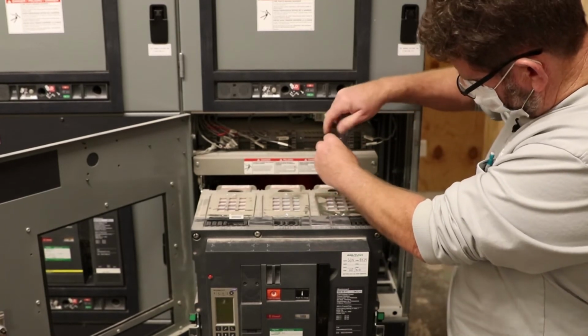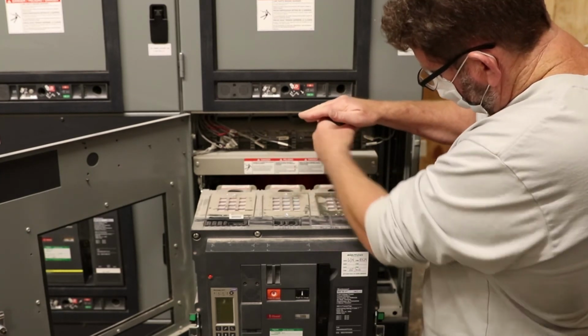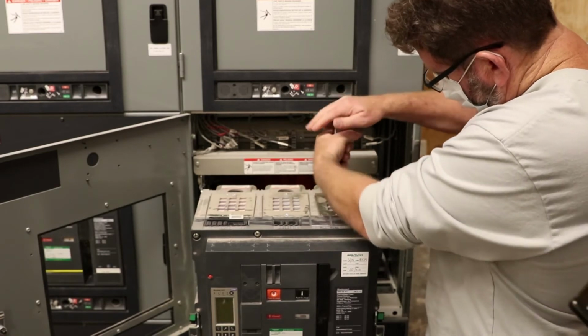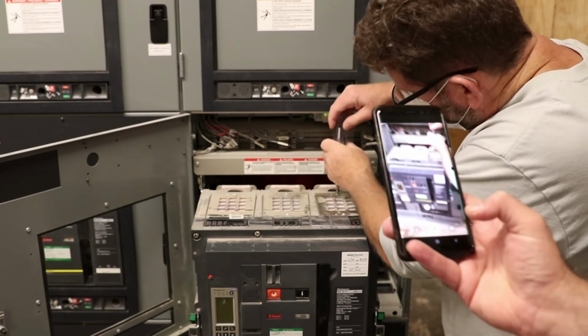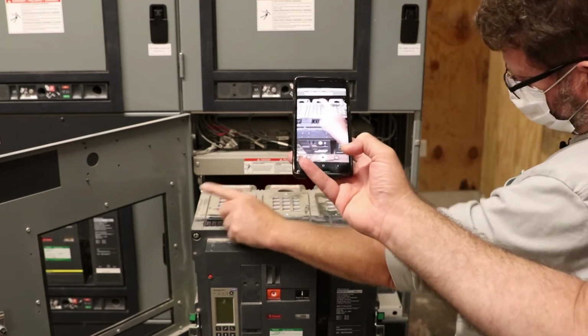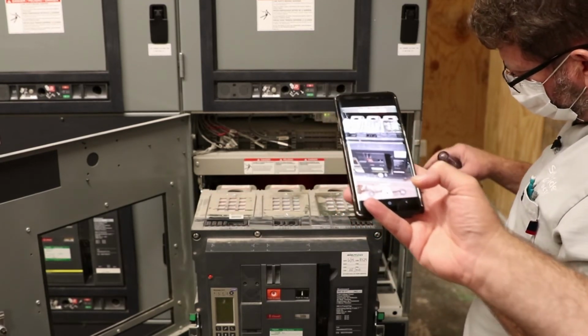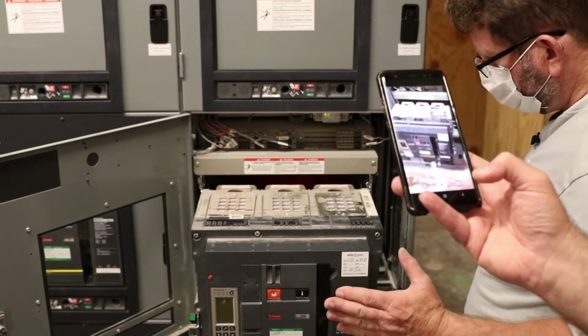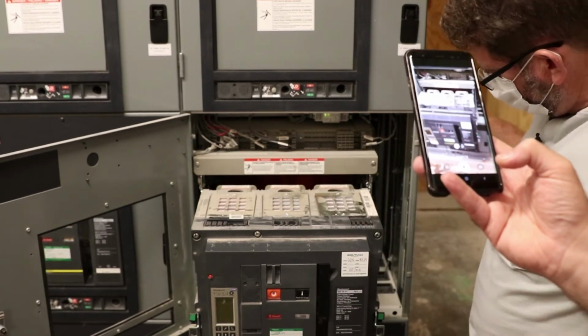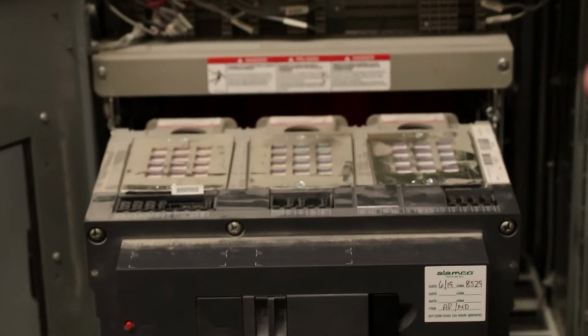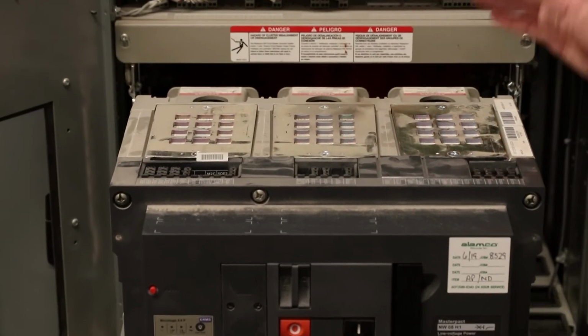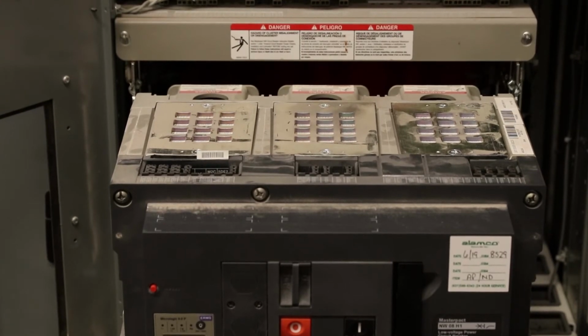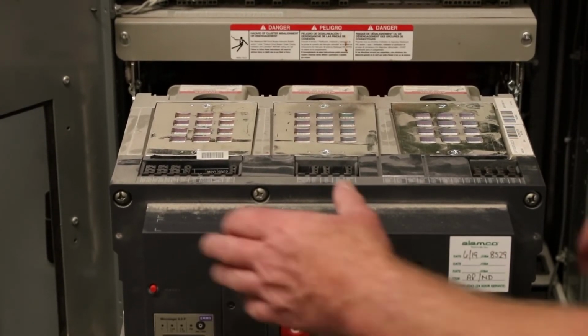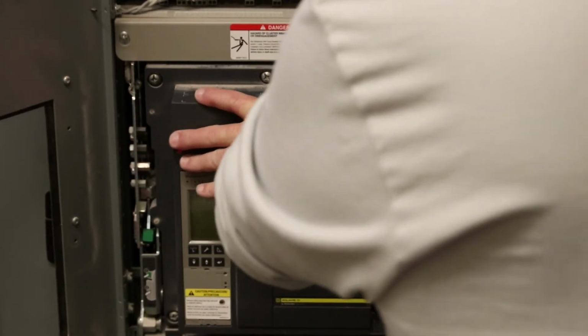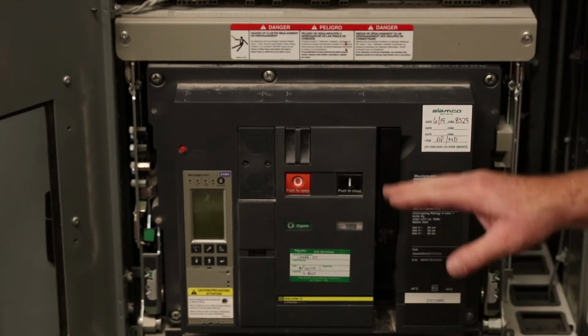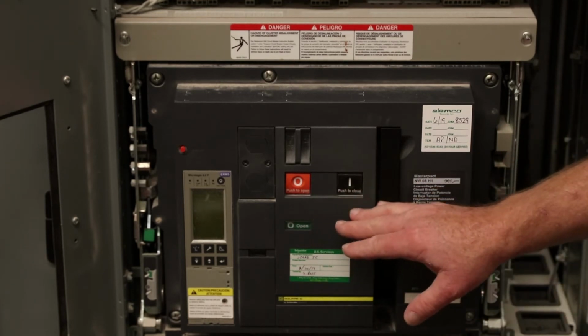And if you noticed or not, when I pulled the breaker out, you can see behind it, there's shutters. As the breaker goes in, there's an operating arm that'll move the shutters to the right or to the left a little bit, exposing the stationary contacts in the cell, and the breaker will push the whole shutter back around those stationary contacts to make the connection. When the breaker comes out, the shutter is closed, so you don't have any exposed 480 volt here. You can't rack the breaker in closed. That's why I opened it when it went in.